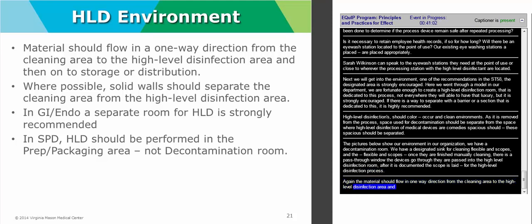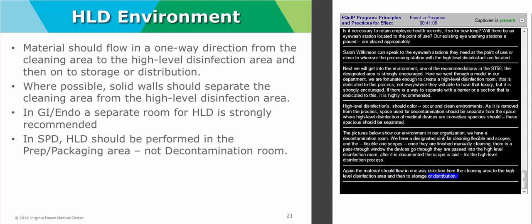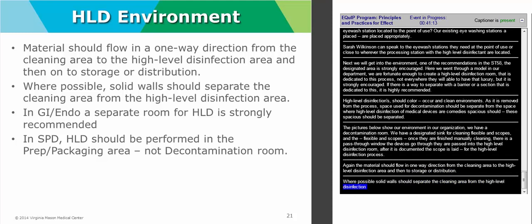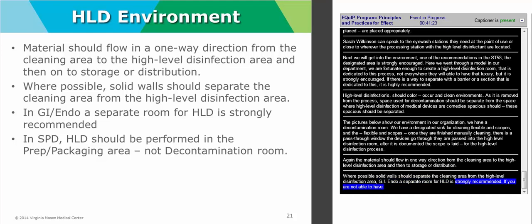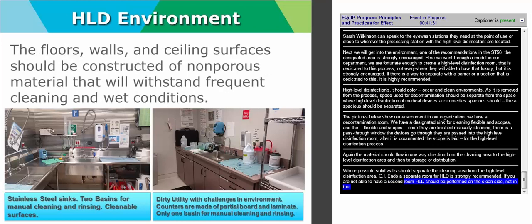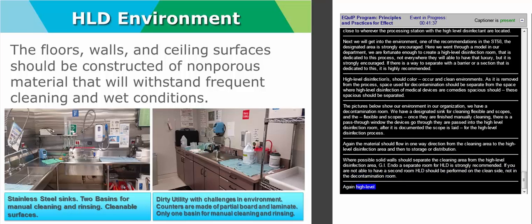Where possible, solid walls should separate the cleaning area from the high-level disinfected area. In GI endo departments, a separate room for high-level disinfection is strongly recommended. In the sterile processing department, if you're not able to have a separate room, HLD should be performed on the clean side or the prep and pack area, not in the decontamination room. Again, in the high-level disinfection environment, the floors, walls, ceilings, and work surfaces should be constructed of non-porous material that will withstand frequent cleaning and wet conditions.